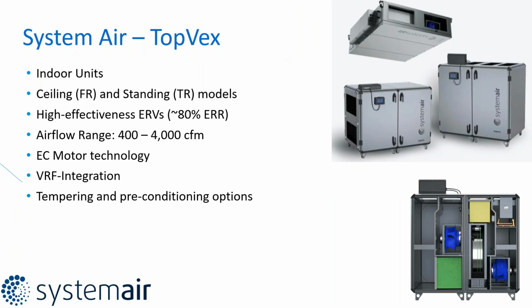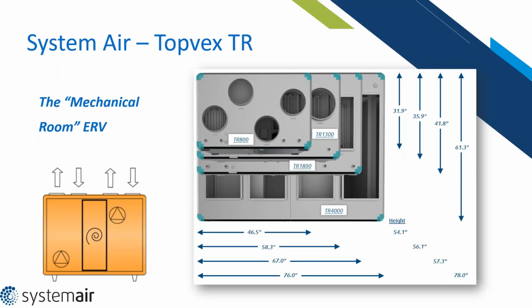So this wheel is also used in our TopVex unit. In both of these ceiling and standing models that are intended for indoor mounting, we get high effectiveness from that wheel that I just showed you. We can also do a sensible core out of this, and eventually we're working towards an enthalpy core. These are airflow ranges of 400 to 4,000 CFM. It has EC motor technology, and we can integrate these with VRF as well. It's just a little bit different because it's mounted to the unit rather than inside the unit at the factory. These do come with tempering, or you can use it as just a preconditioner.